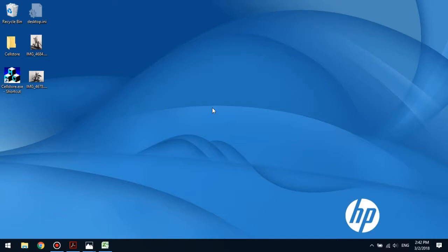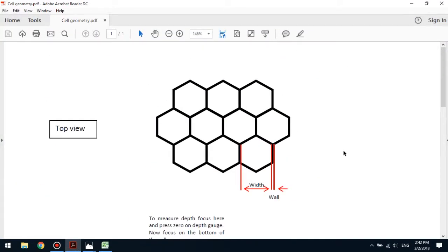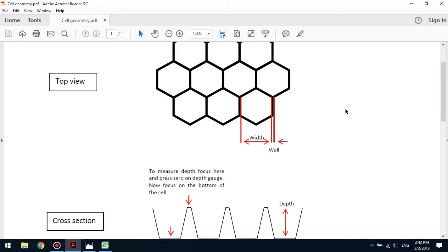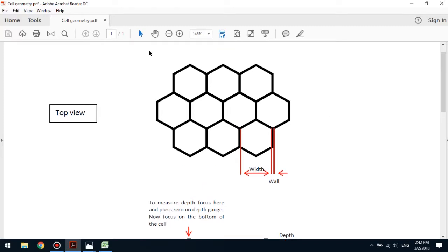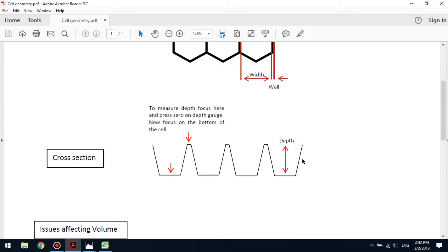Before we start, I'd like to take a quick look at cell geometry. This will help us better understand what it is that we're going to be measuring. Here we have a top view of an anilox cell and also a cross-section view. These are the areas that we're interested in: the cell width, which is the cell opening, the cell wall, and also the cell depth.